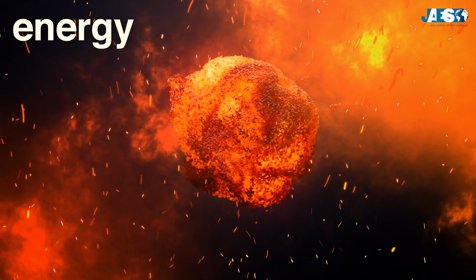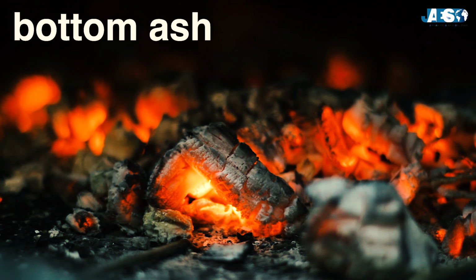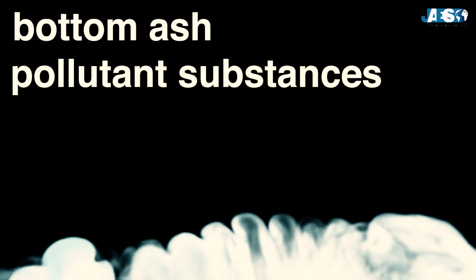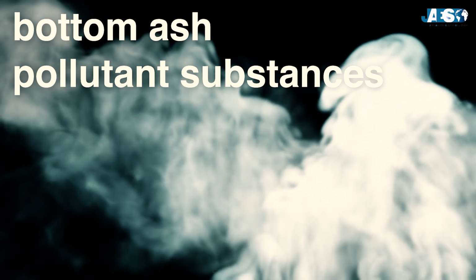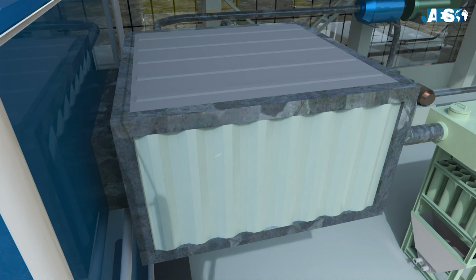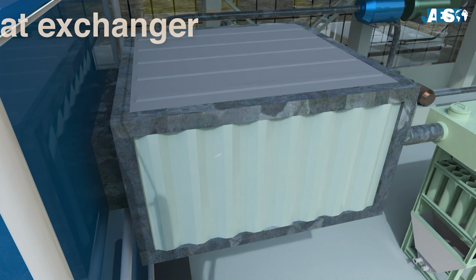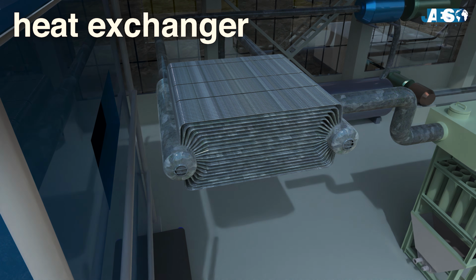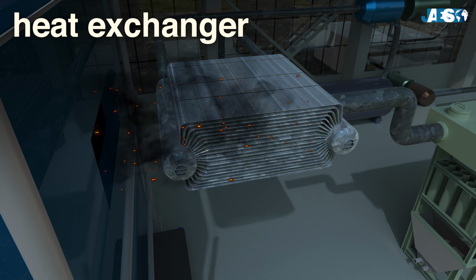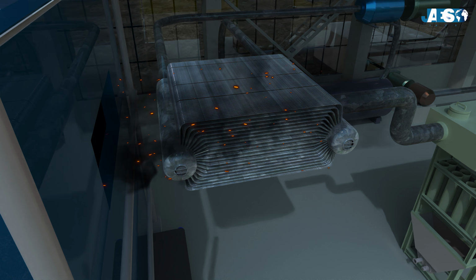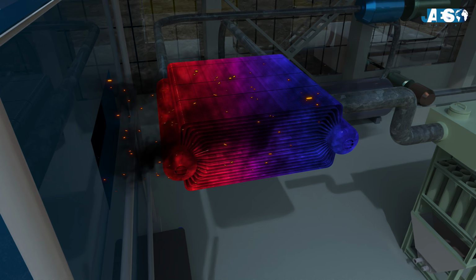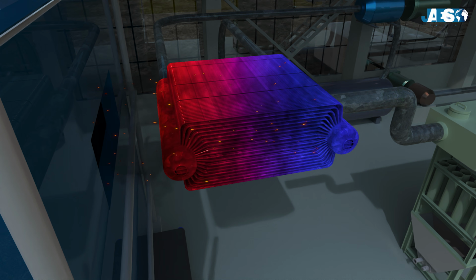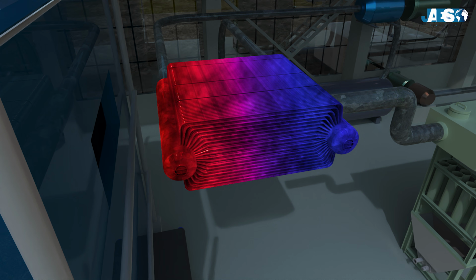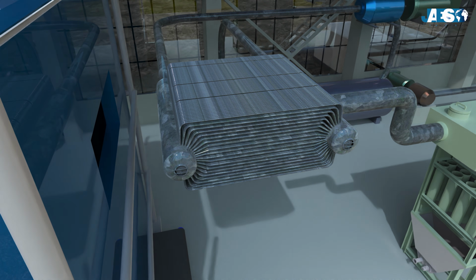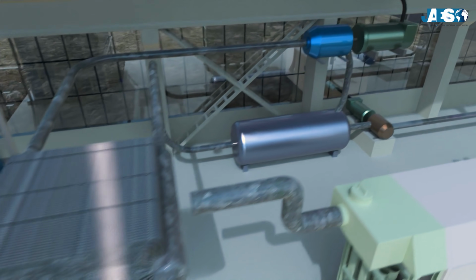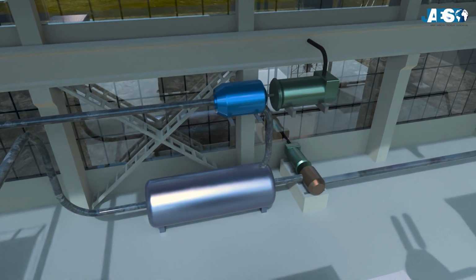The two byproducts are bottom ash, which must be disposed of, and pollutant substances in fumes, which must be filtered out. The fumes then pass through a big heat exchanger, a very important process, where the first real energy extraction takes place. Here, a water circuit absorbs the energy of the burning fumes and transforms it into a high-pressure, high-temperature stream, which can be used for two purposes that can coexist in a single plant.